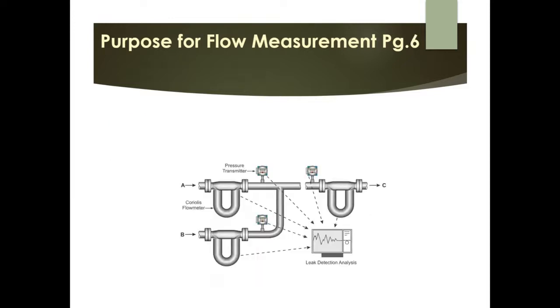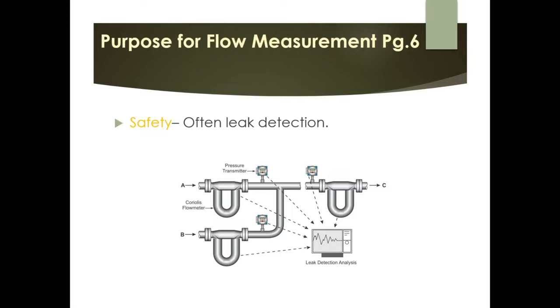The third purpose is safety. We often use flow transmitters as leak detection devices — for example, summing meters on a pipeline where a discrepancy indicates something has been lost or introduced into the system. Flow meters or flow switches are also used on pump seals with a purge gas; if the seal lets go, the purge gas flows and sets off a flow switch.